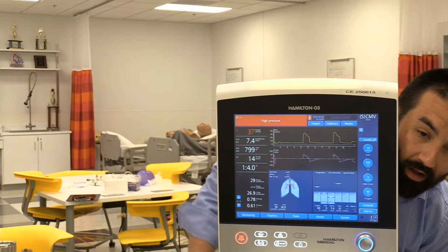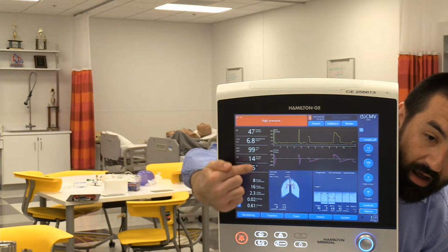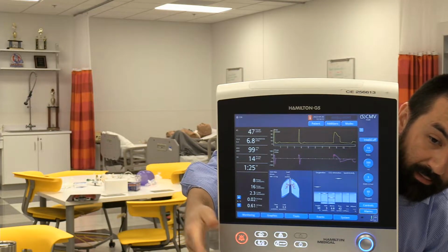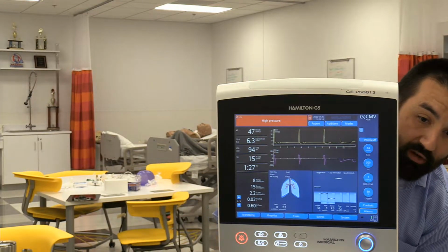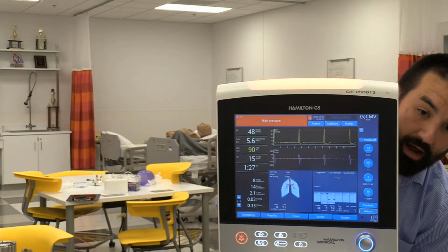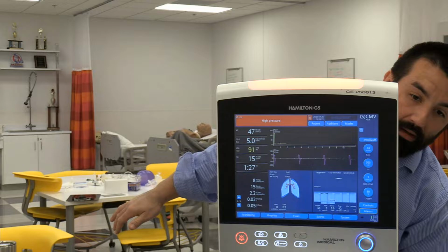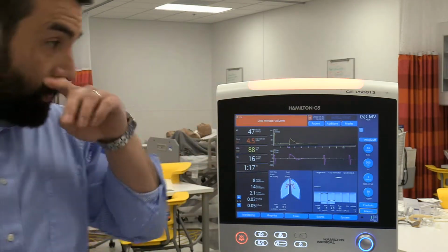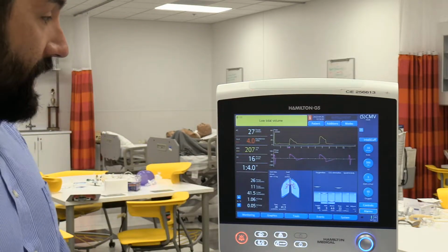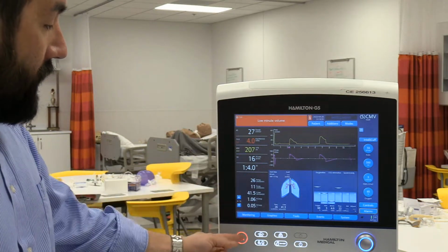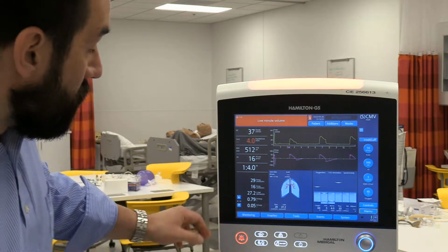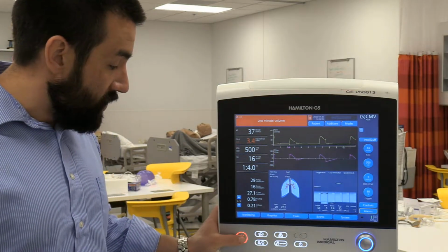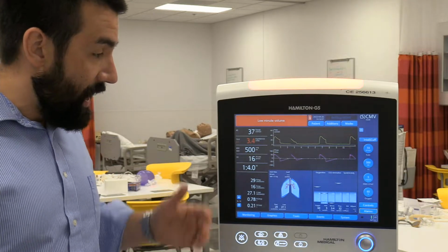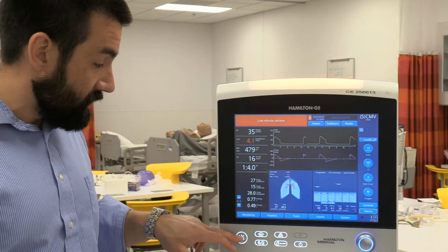So if you see, I'm holding my lung, you can see I'm hitting my high pressure, and it's dumping the breath. My tidal volume's not delivered. It's prematurely pressure cycling the breath. So it's still flashing, it's still doing everything, dumping that breath, opening the safety valve. It's flashing red, so a high priority alarm, but it's not making that audible noise. You can see the yellow, a little bit lower priority. The patient's ventilating here again. Everything was silenced. You wouldn't want to leave that silenced and step out of the room. So by hitting that, it's going to reactivate or re-enable all your alarms.